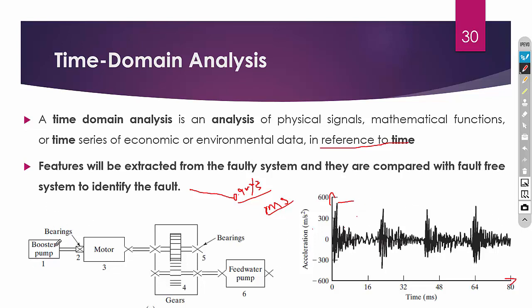The signal taken from a system containing a booster pump, motor, gearbox, and feedwater pump contains all the vibration components of the entire setup. The sensor placed on the bearings captures vibrations from the booster pump, motor, gearboxes, bearings, and feedwater pumps all together. With this combined time domain data we can conclude there is some fault in the system, but we cannot identify the nature of the fault or the specific component where the fault occurred — whether in the pump, motor, gearbox, or bearings. That is the drawback of time domain analysis.